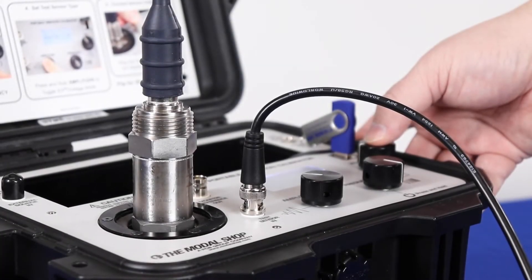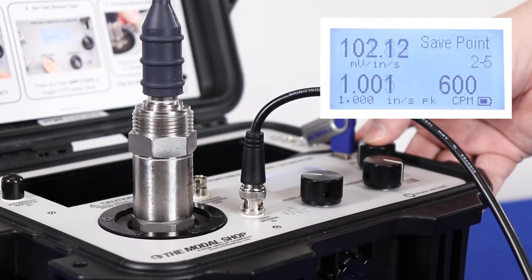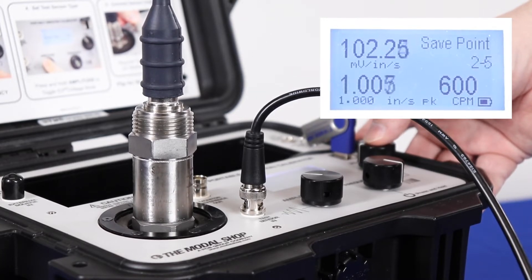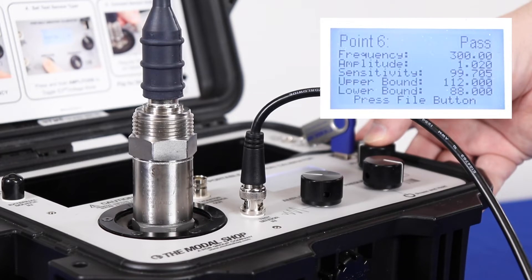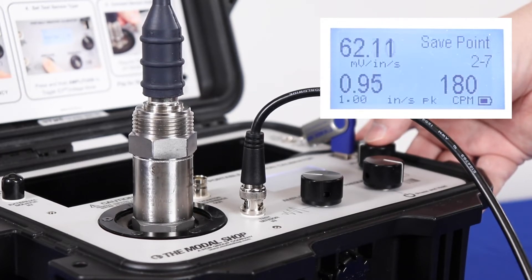For brevity, I'll just show the final test points of our sweep starting at 600 cycles per minute, 1 inch per second. The output of the 190501 is 102 millivolts per inch per second and that passes calibration. Moving on to 300 cycles per minute at 1 inch per second, the output is 99 millivolts per inch per second, which is within tolerance — so that also passes calibration. We're starting to see the roll off at 180 cycles per minute; at 1 inch per second our output is 62 millivolts per inch per second and that also passes calibration.